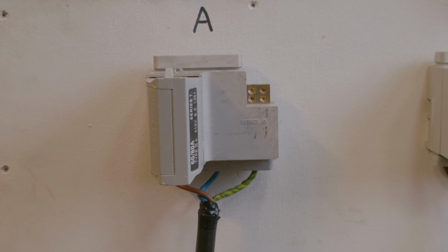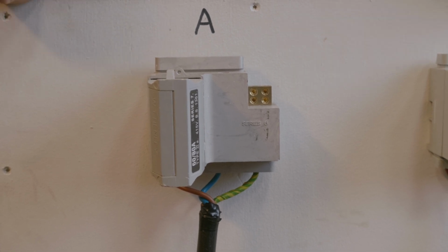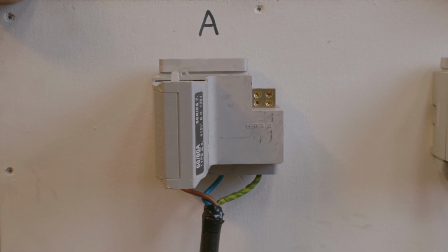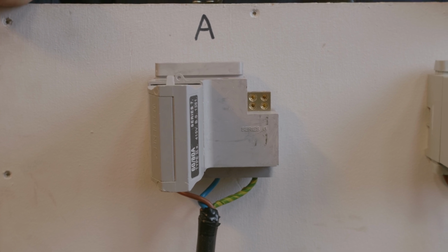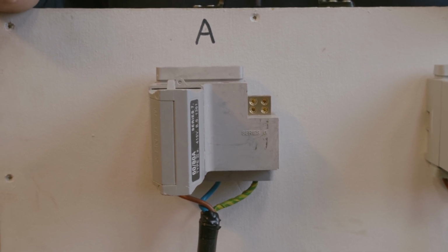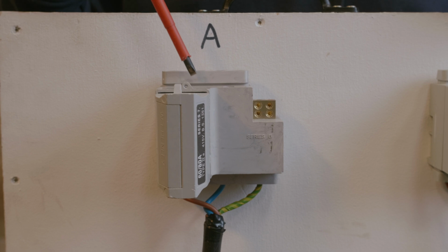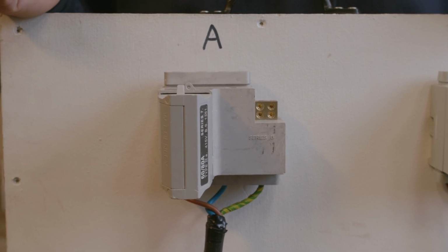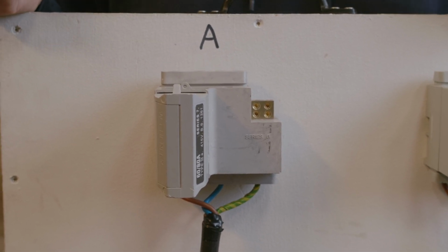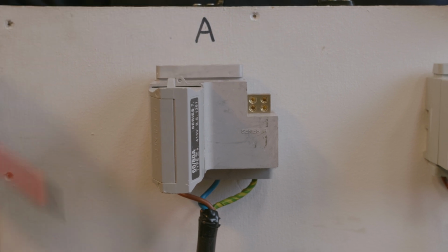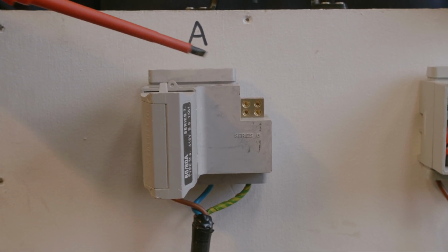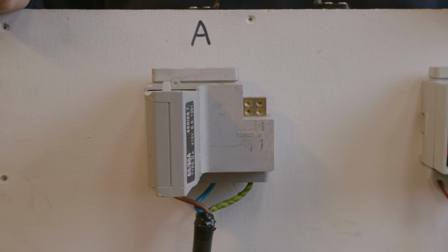But basically, the earthing arrangement here for A is a TNS system. A TNS system is where we have a separate neutral and earth all the way back to the supply transformer, and that is separate all the way up to the cutout, and then it's going to be separate going off to the installation as well.